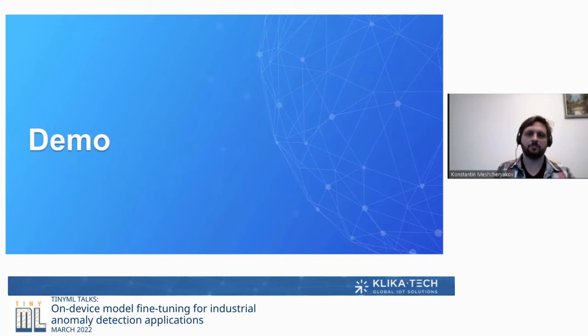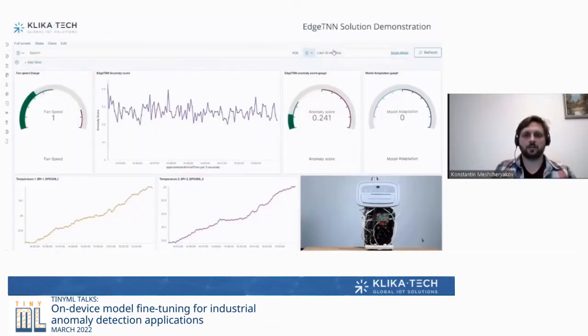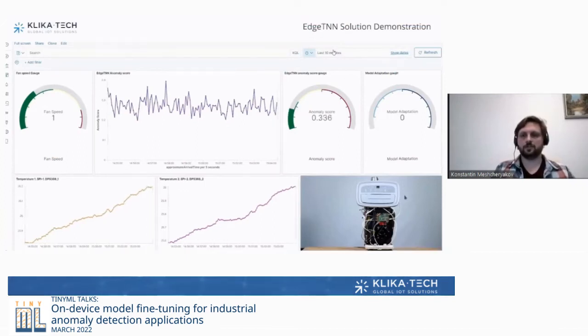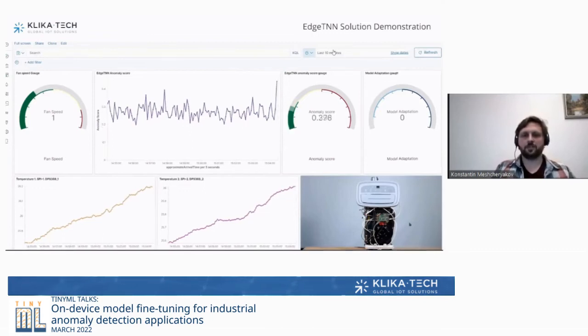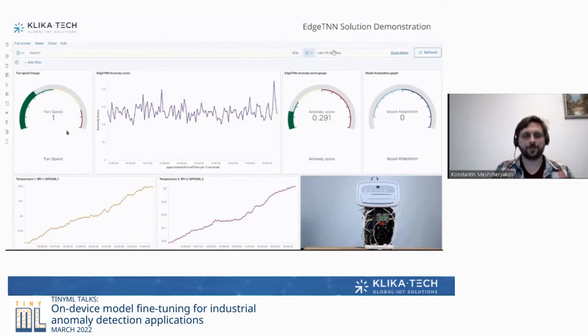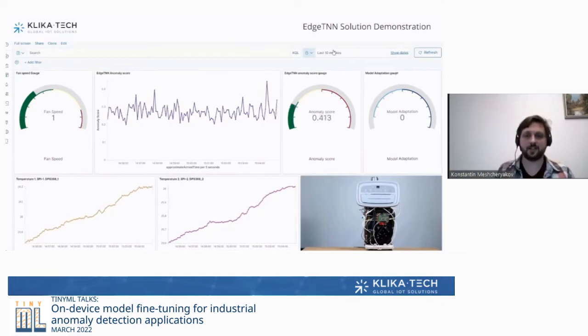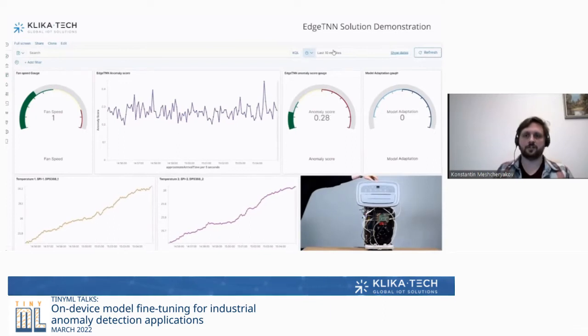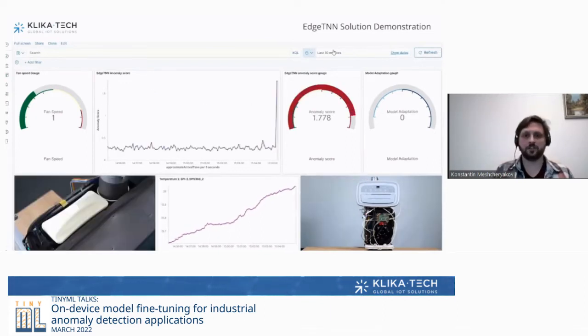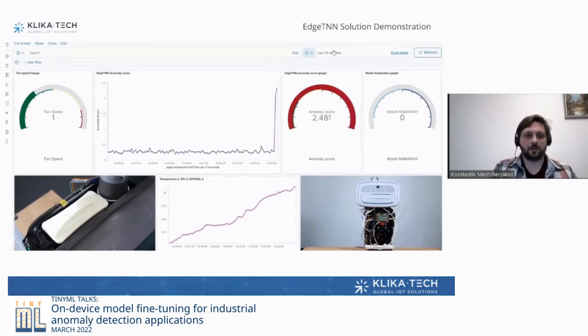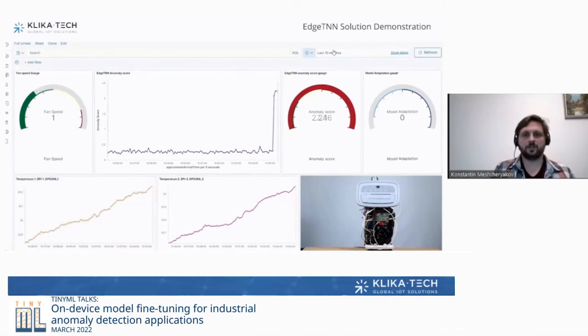Now I'll show a demo with actual hardware. In the lower right corner you can see the equipment — an air conditioning unit. You can see data from different sensors like temperature, the current operation mode, anomaly score, and whether the model is adapting. We introduce an anomaly by emulating exhaust clogging, preventing air from going out. We see a significant jump in the anomaly score — so it works on the device itself.